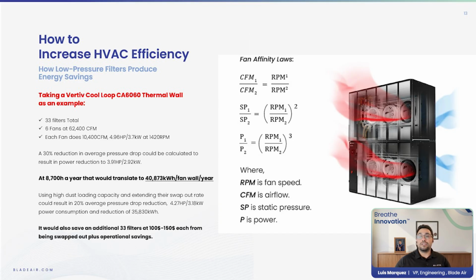So how does low pressure, high dust holding capacity reduce energy and maximize efficiency? Let's take, for example, a Vertiv CoolLoop thermal wall. The particular model that I've chosen here has 6 fans, and each of these fans operates at 1420 RPM, and they each move about 10,400 CFM at 4.96 horsepower.